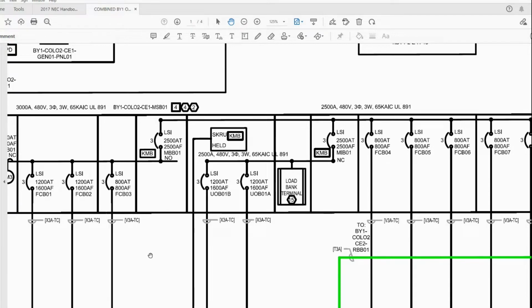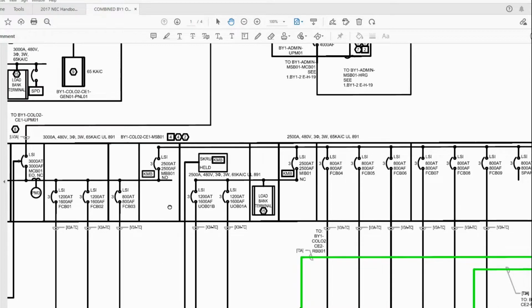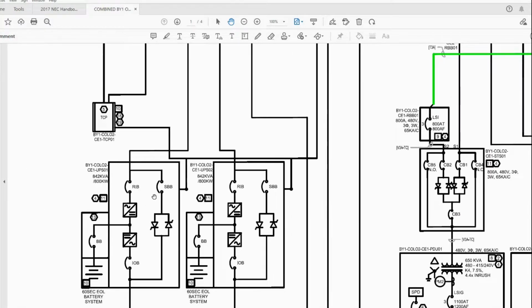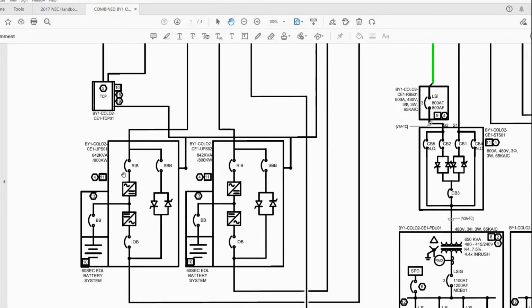Now you might be asking, why would we need a Kirk key system on this? And the reason why is we have a UPS. This UPS here is a paralleling system, 800 kW each. Each one of these UPSs takes in 480 volt AC and outputs 480 volt AC. But in between, we got this DC link. So essentially what we have is a rectifier and an inverter. The rectifier is to charge up the battery system, and when we lose utility feed, the batteries feed back into the DC link and continue the UPS outputting 480 volt AC.